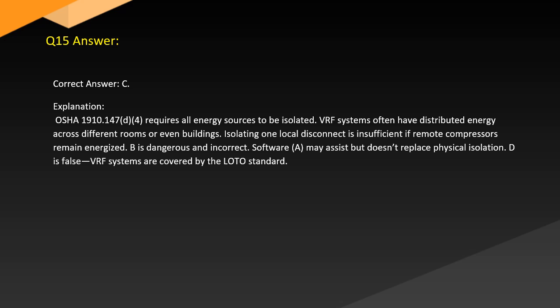Answer. Correct answer: C. Explanation: OSHA 1910.147 D4 requires all energy sources to be isolated. VRF systems often have distributed energy across different rooms or even buildings. Isolating one local disconnect is insufficient if remote compressors remain energized. B is dangerous and incorrect. Software may assist but doesn't replace physical isolation. D is false. VRF systems are covered by the LOTO standard.